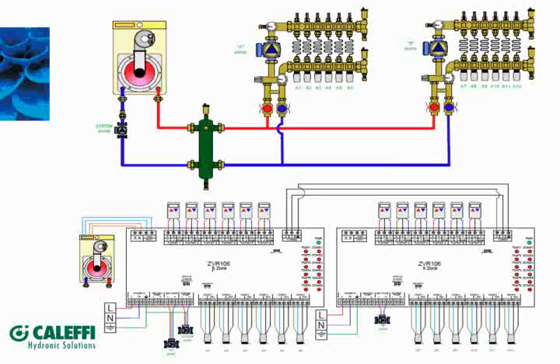One thing to point out there too is that we did come out with a low current draw thermoelectric actuator last year. It only pulls 250 milliamps at pull-in, and then drops down to about 100 milliamps. So if it is an issue with the current draw, I'd ask you to look at our 6564 series, which has real low current draw for a thermoelectric actuator. And that was the key, because guys said we wanted to put multiple actuators on one. How can we do that?